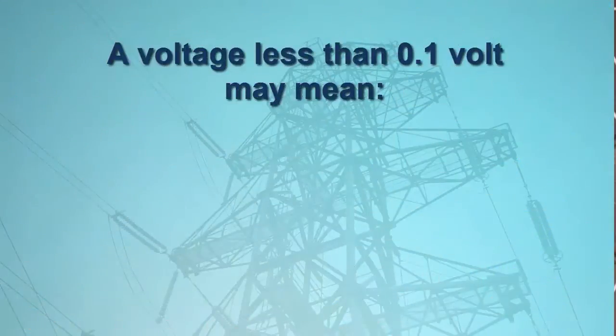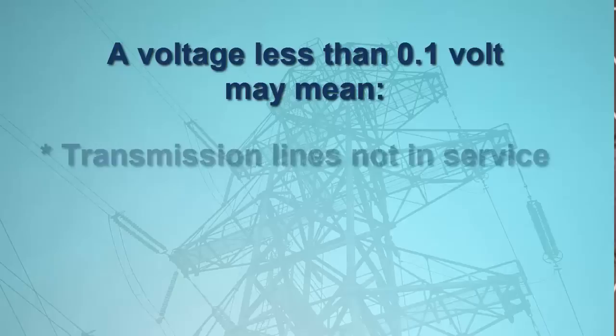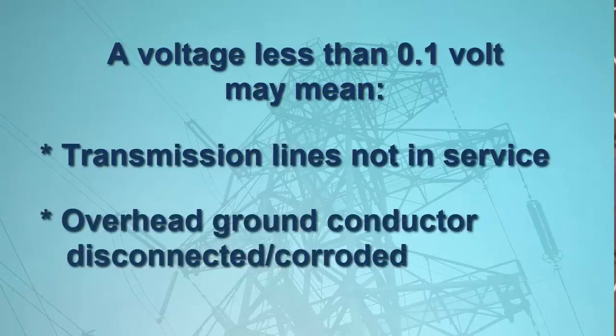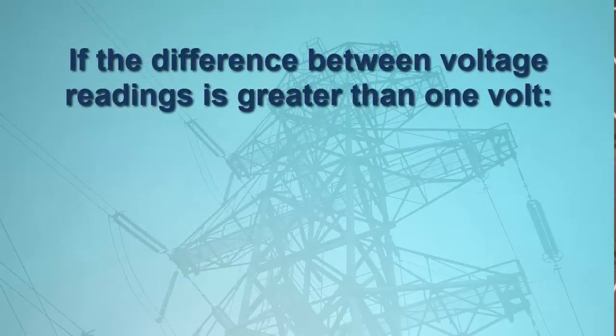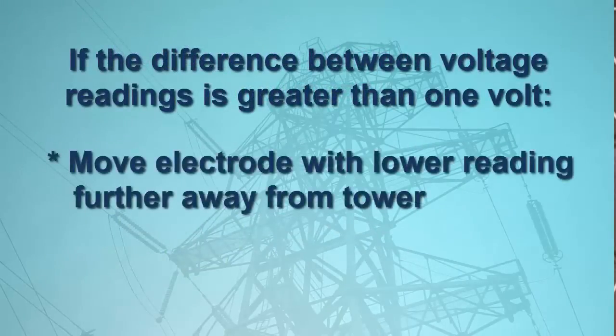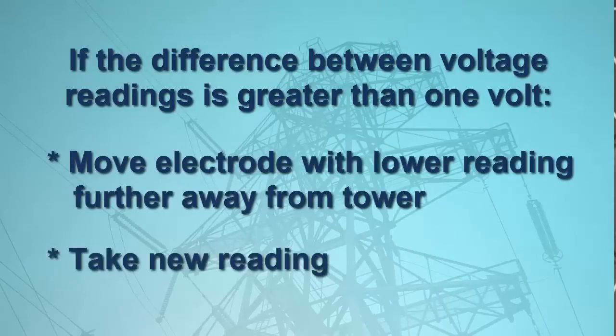If the voltage readings are below 0.1 volt, this likely indicates that the tower's transmission lines are not in service, or that the overhead ground conductor is completely corroded or not connected. In this case, the total tower current will also be close to 0. If the difference of the reading exceeds 1 volt, move the electrode with the lower reading further out from the tower and take a new reading. Too large a voltage difference between the electrodes may invalidate any results we obtain from our subsequent testing.